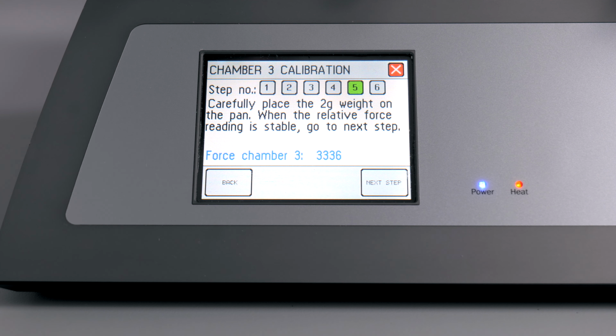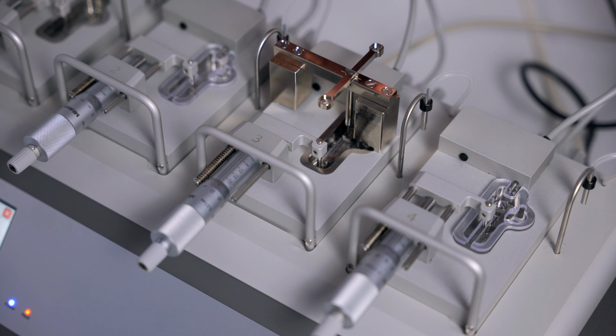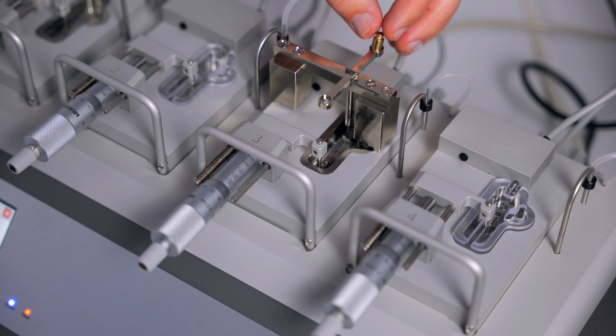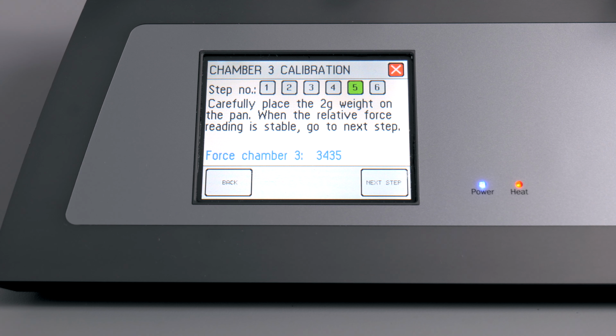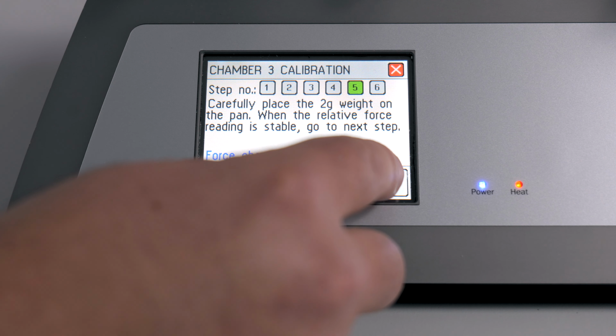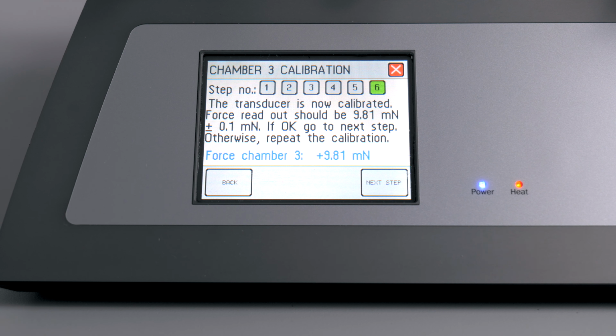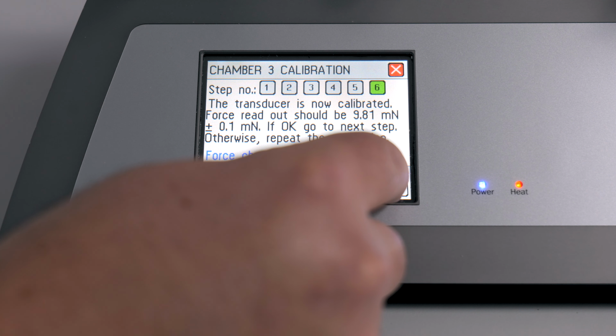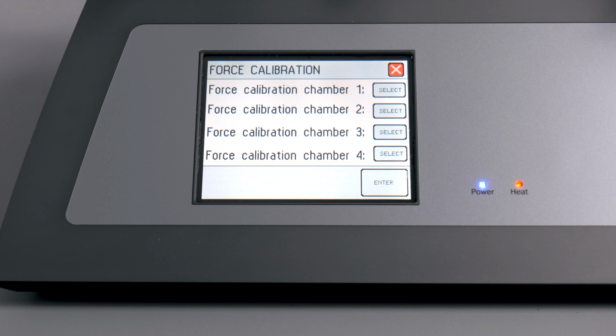Now we are asked to add the 2-gram weight. Make sure you place it in the back pan to kick the T-balance forward. After giving it 10 seconds to stabilize, select Next Step. Again, it should be approximately 9.81. If it's within the range of 0.1 millinewtons, you can select Next Step. This will complete the calibration.